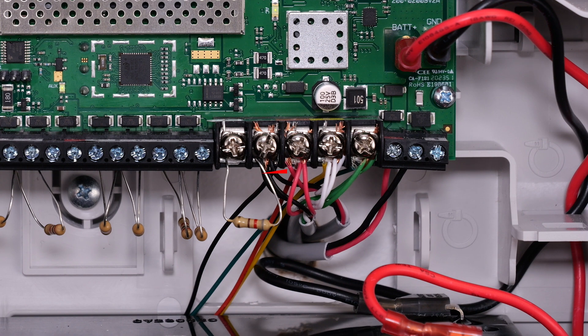Moving down the line of screw terminals, any sounders being installed will be connected to the bell and ground terminals. An 820-ohm resistor — gray, red, and brown — will supervise these terminals. The output provides 10 to 13 volts DC at 2 amps max. A battery must be installed to the panel to support the 2-amp max current for a sounder, because the battery provides the current for the sounder.